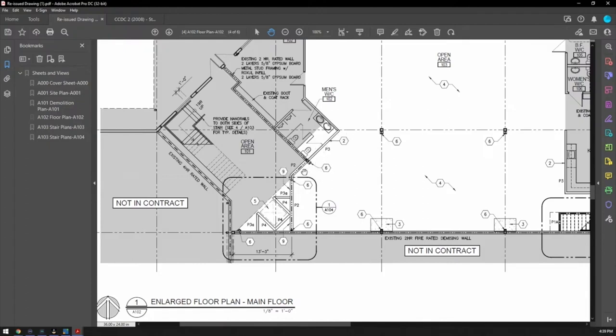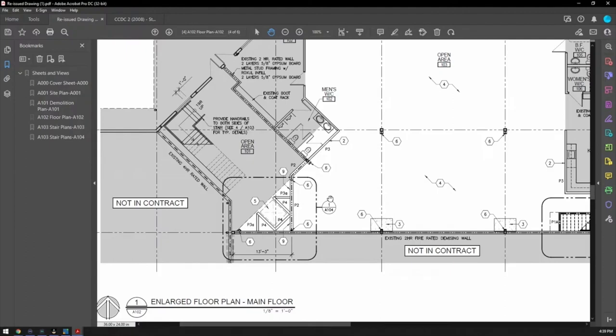Anything that has fire rating lines goes to underside of structure. It always goes from floor to floor, underside of structure. That fire rating is a tell-tale or tell sign.